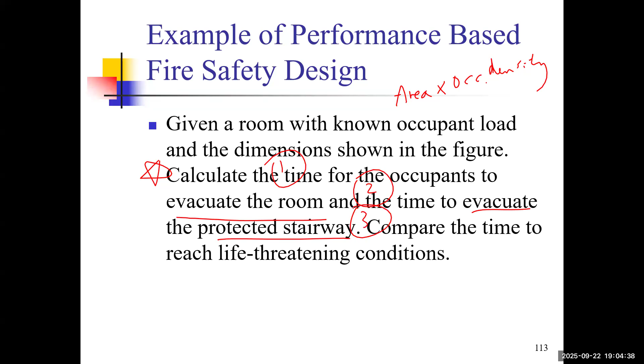Length of room is 10 meter, width of room is 10 meter. Length of protected staircase is also 10 meter. We assume that here we have another 10 meter. And floor area of the room is 10 times 10, which is 100 meters square. Density from the table, or is given in the information, is 0.9 person per meter square. So in some of the calculation, you can also see, if you multiply it together, the units will be cancelled out and then leave you with the number of occupant people.